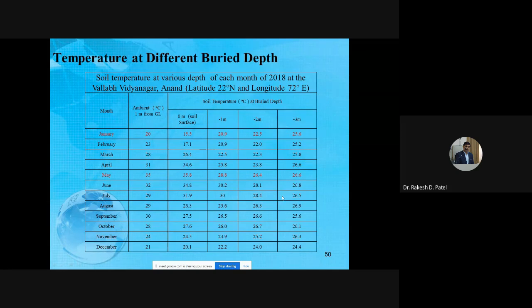From this observation table, you can easily see the approximate temperature at buried depth: at a 3 meter depth, approximately 26 degrees temperature is constant throughout the year. This energy is used for the cooling as well as the heating of any building or room. So from the temperature measuring probe, I validated the buried depth as well as the buried temperature. Buried depth is 3 meters and buried temperature is 26 degrees centigrade, from this experimental analysis of my heat exchanger.